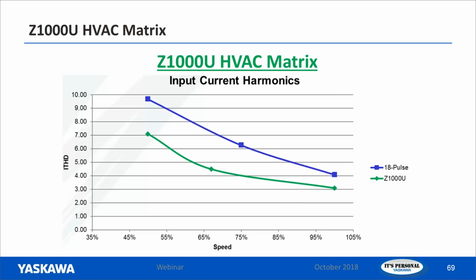Here's a depiction of comparing the Z1000U to what could be argued as the other best option, and that would be 18 pulse. Over here on the left, we've got our current distortion, and on the bottom, we've got speed from left to right. The blue line is 18 pulse, green is Z1000U, and as you can see, there's no point on the line where green is higher than blue. High is bad, low is good. We've got our distortion over here on the left.